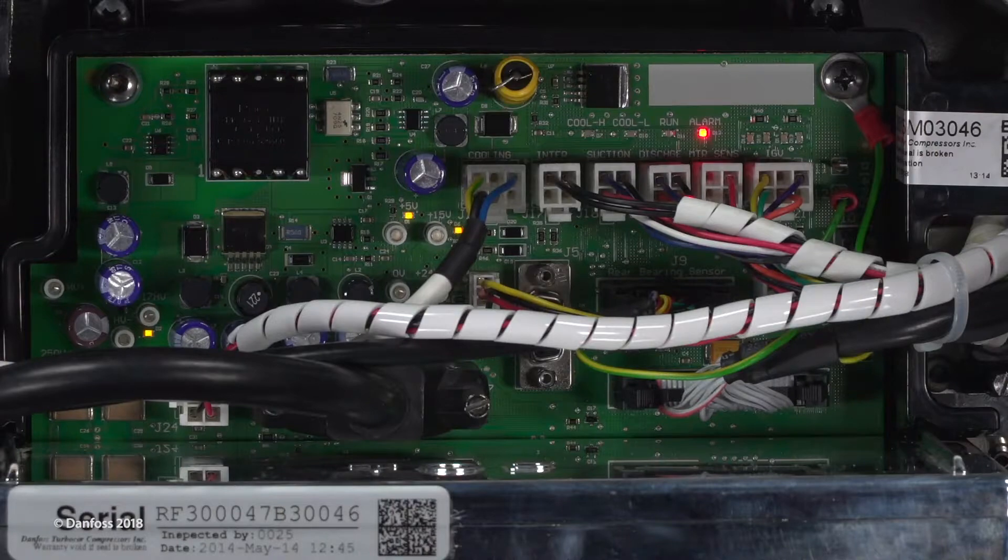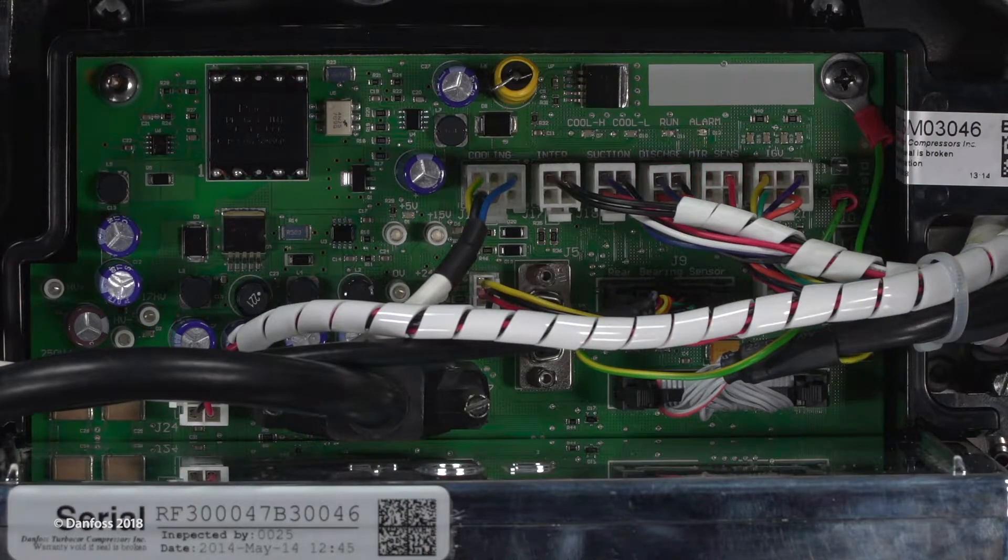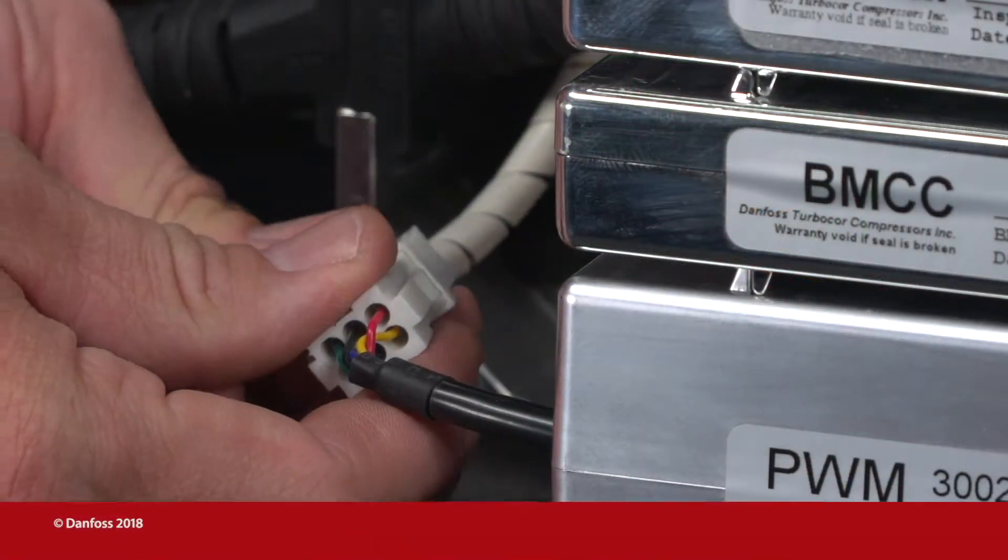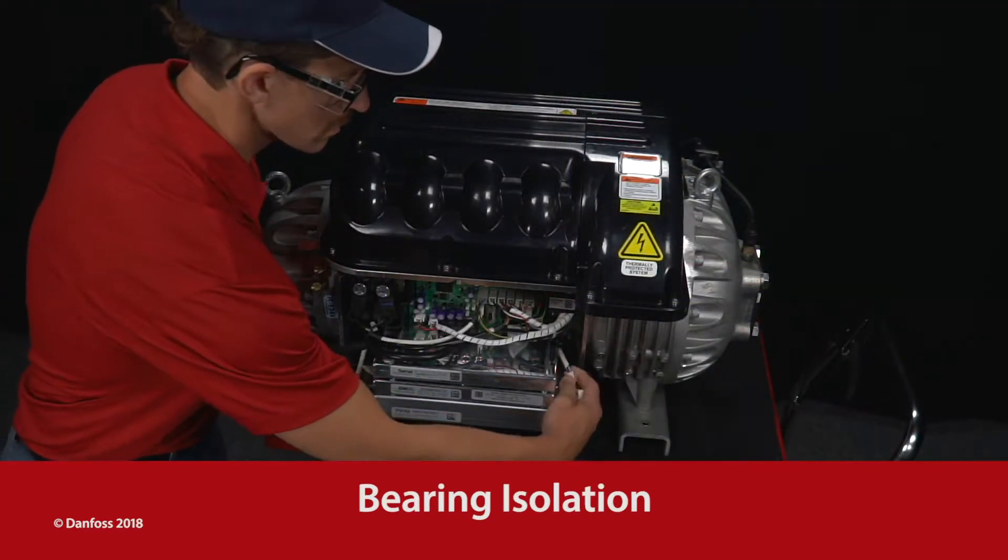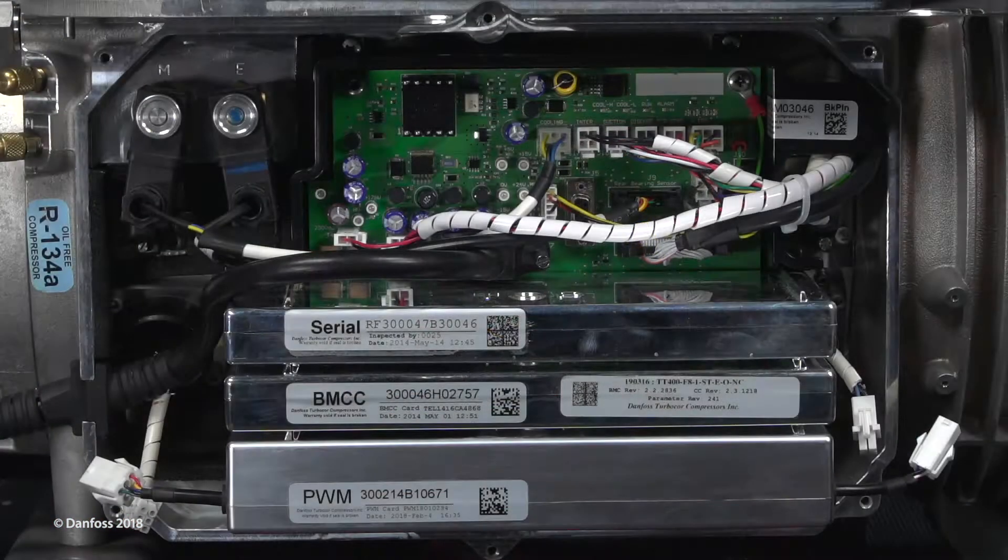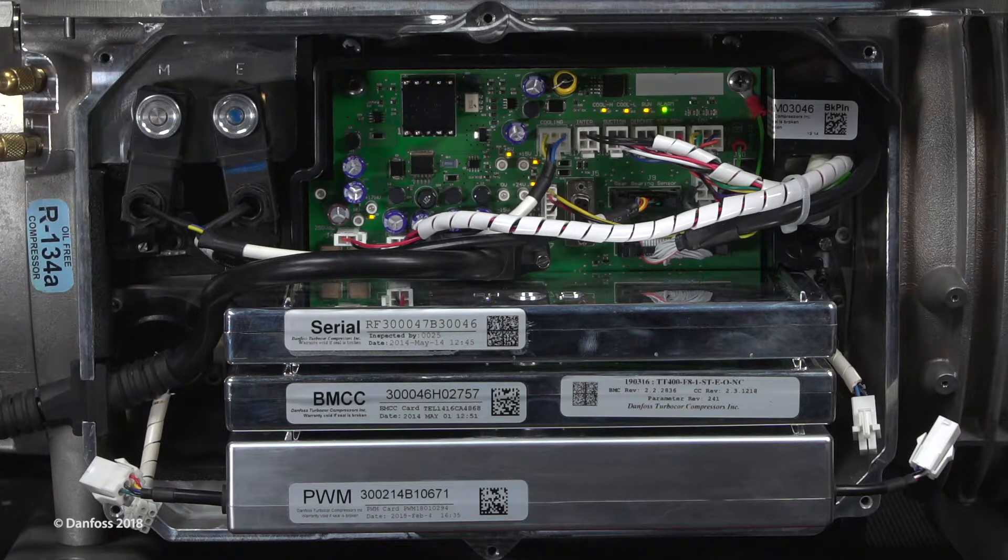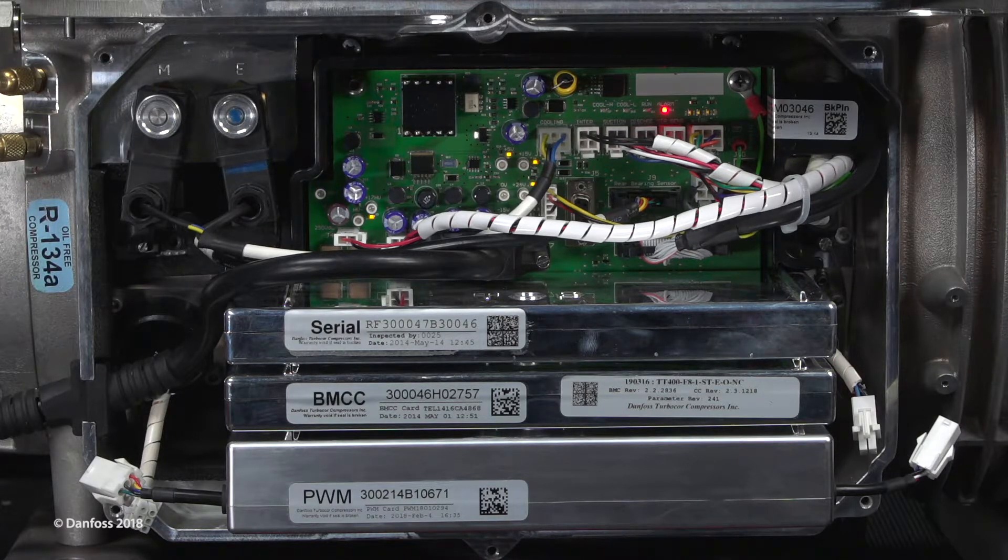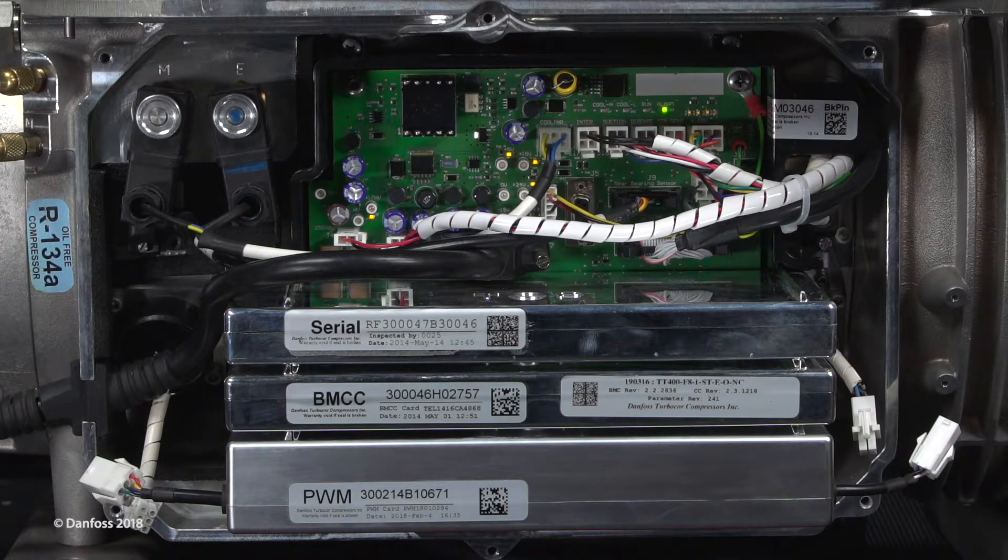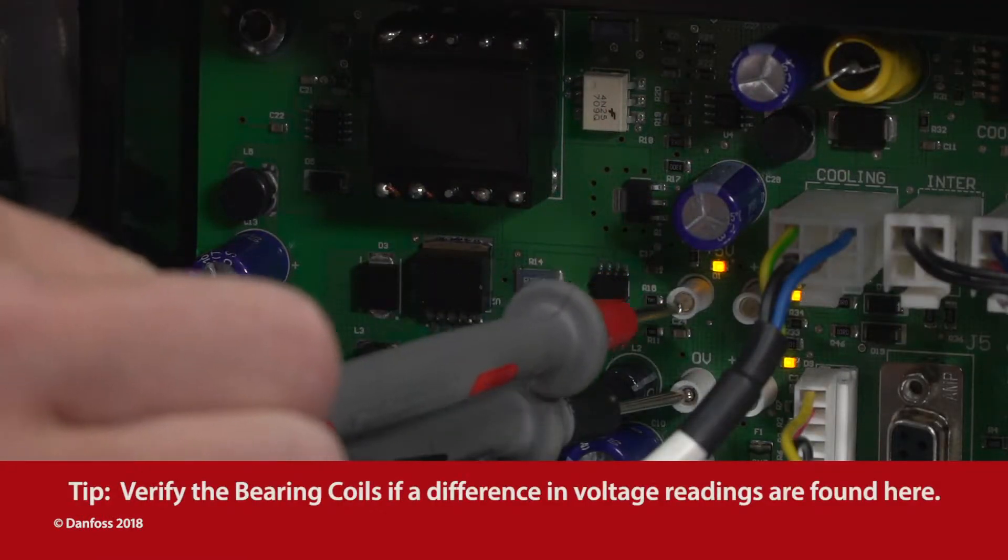Wait for the LEDs on the backplane to turn off. Disconnect the PWM output cables from the bearing feed-throughs. Reapply power to the compressor and wait approximately one minute for the compressor to complete the startup sequence. You may then verify the voltage test points on the backplane again.